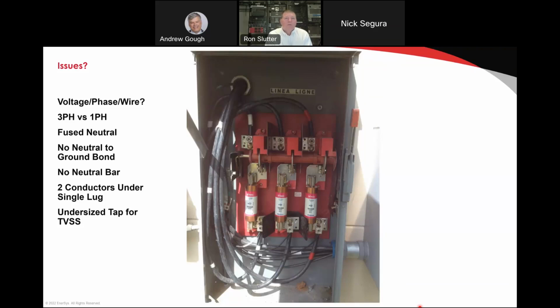Is it okay to have an external ground ring and put towers and fences and satellite dishes on it and then just bring it into the building at one point? So the general rule is if it's outside, keep it outside, which is why we have the ground ring around the building. So I'm completely fine with you bringing a fence to the ground ring outside, your HVAC units down to the ring that are outside. Your generator ring should be tied into the ring around the building. The tower grounds should be tied to the ring. Your AC service should go out of the building to the ring and not to the MGB, because we want it to go out to where it will be absorbed before it will be distributed to the equipment on the MGB. So general rule, if it's outside, keep it outside.